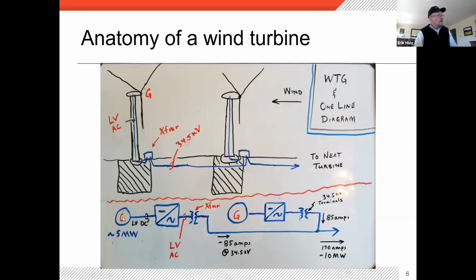In a one-line representation of this, you have a generator—I'm showing 5 megawatts for this example. Current generator technology can go higher, but it's a convenient number to show what I'm conveying. So it goes from the generator through an inverter, then through the inverter transformer, and the cables are run underground. The first one has 5 megawatts in. These cables are actually 3 bundled together, combined about as big around as your wrist. On land they'd be buried underground; in the ocean, they're on the ocean floor, and if possible buried a couple feet down to protect them from being disturbed by anchors or whatever.